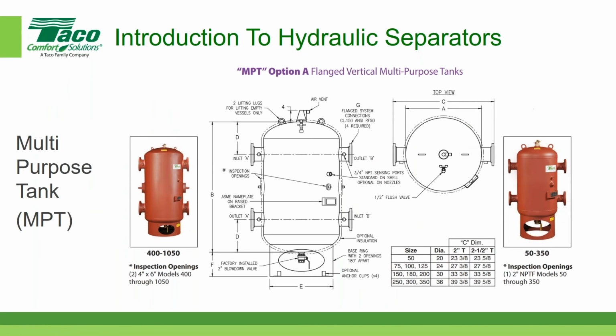Okay, let's look at another device, which is called a multi-purpose tank. Now, you can get a multi-purpose tank configured as a hydraulic separator and also as an air and dirt separator with Pall rings. Now, in many systems, there needs to be a minimum volume of water in the system. So, for example, let's say that it's a boiler system, and for every roughly 10 to 12,000 BTUs per hour of boiler capacity, let's say that they needed somewhere between 3 to 5 gallons per 12,000 BTU. So if you had a 12 million BTU system, divide that by 12,000 and multiply that by 5 gallons per 12,000. That means you'd need about a 5,000 gallon volume in your system.